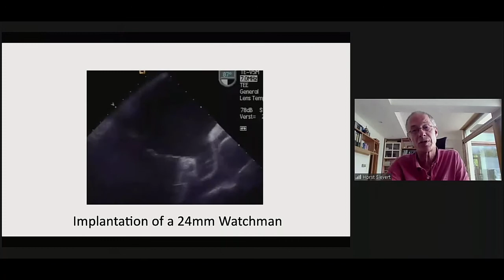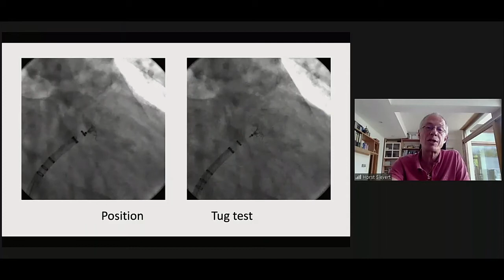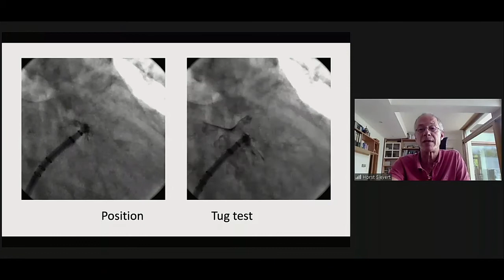So this is the implantation of a 20. We always go for the largest according to these measurements. So that is a 24 millimeter Watchman. We measure residual compression. We do check the position. We do a tug test. That means we check whether the device is in a stable position when we pull.